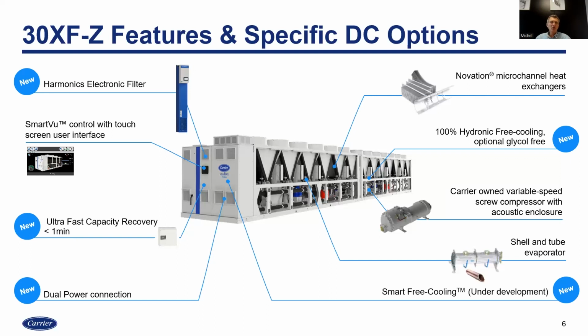I forgot to mention that controls also have a backup battery—we call it an ultra capacitor. This means that during the power transition, the unit control stays alive and doesn't need to reboot, so we can react very quickly as soon as power is back to restart the compressor in the correct mode.